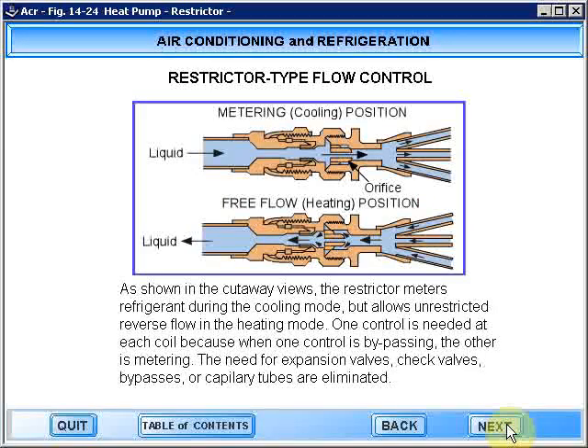As shown in the cutaway views, the restrictor meters refrigerant during the cooling mode, but allows unrestricted reverse flow in the heating mode. One control is needed at each coil, because when one control is bypassing, the other is metering. The need for expansion valves, check valves, bypasses, or capillary tubes are eliminated.